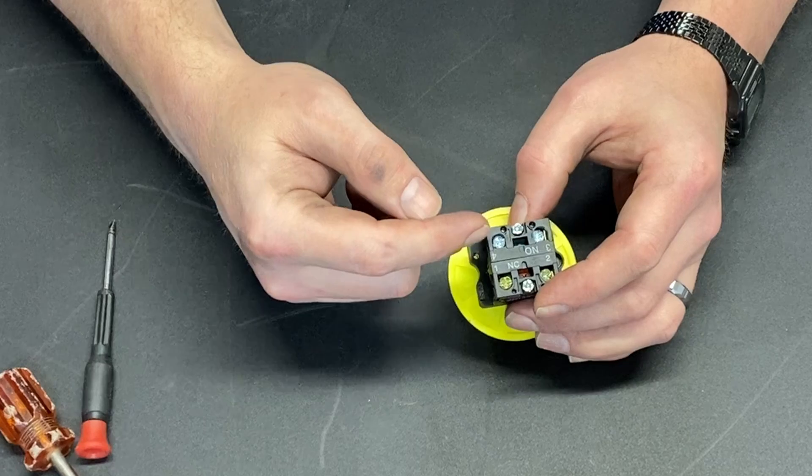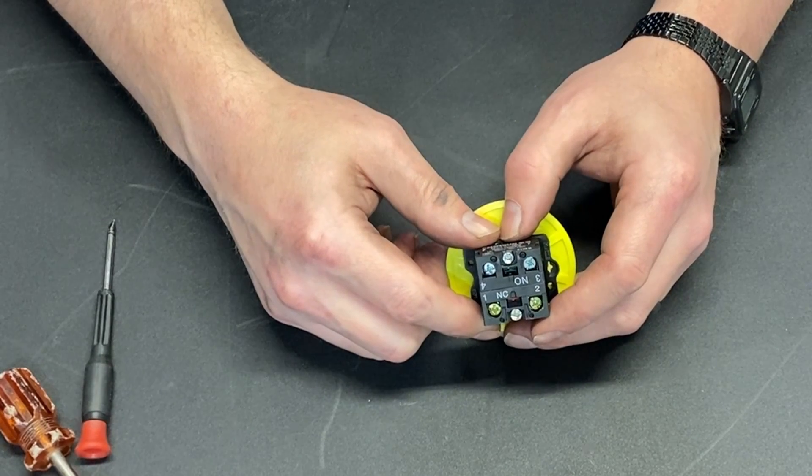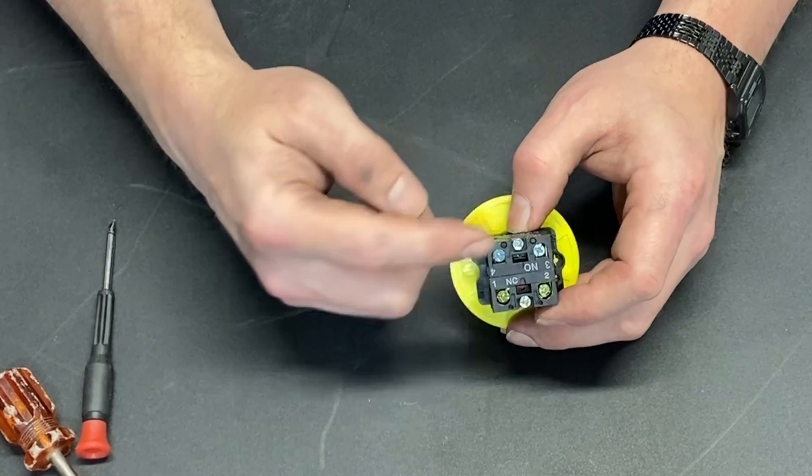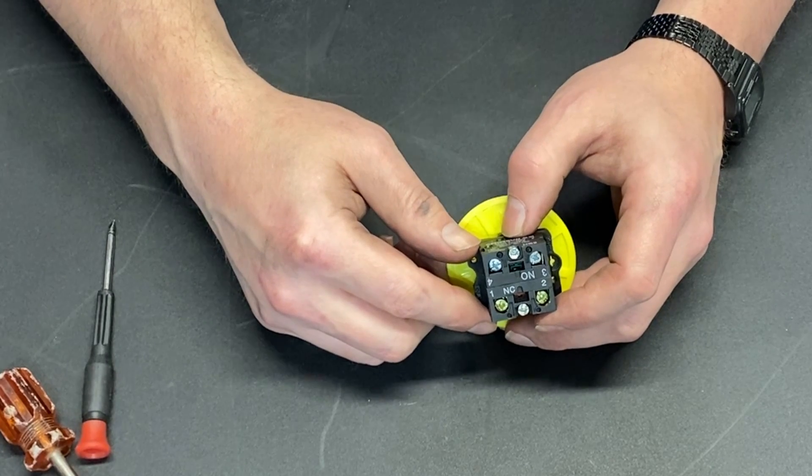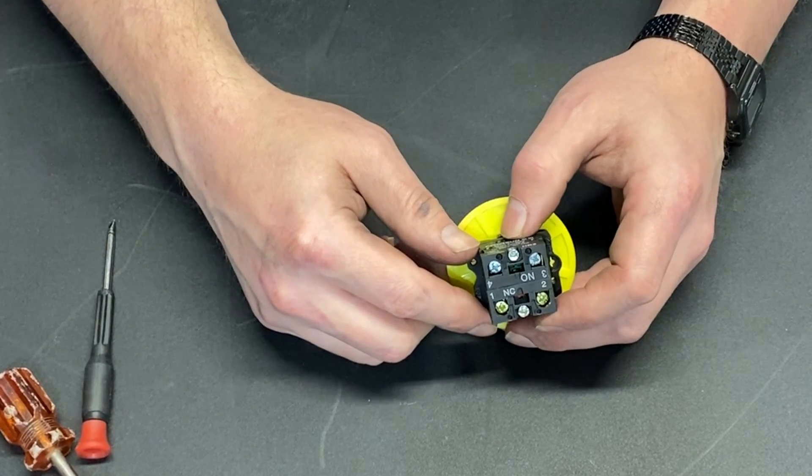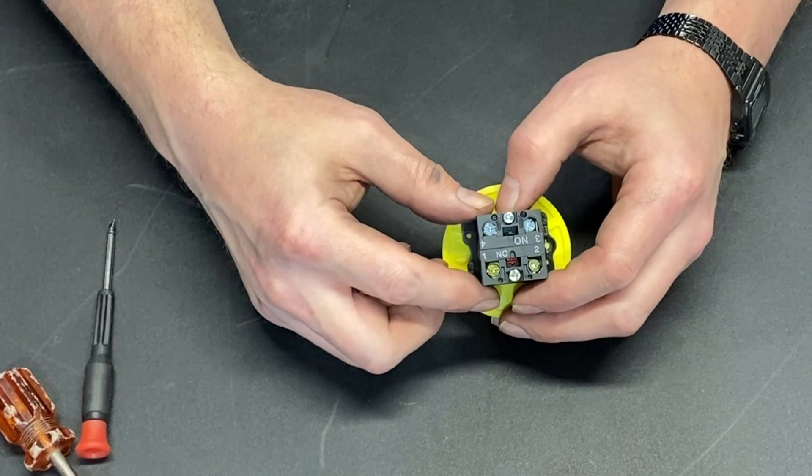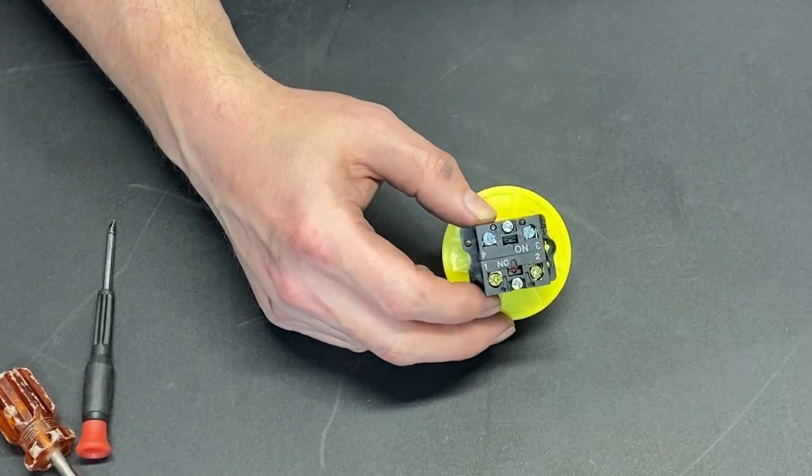This normally open one would be for something else, something that might signify that we have a problem. Maybe that's tied to an alarm. Maybe that's tied to a relay that cuts power to something else. Any number of things could be hooked up with that so that when we're in an emergency situation, something else turns on.